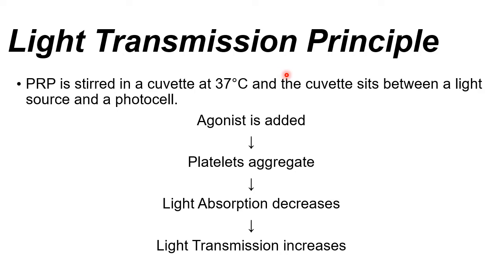Let's discuss the light transmission principle, which is similar to the spectrophotometry principle. We prepare PRP and warm the specimen at 37 degrees Celsius to simulate body temperature and activate the proteins for aggregation. Then we add the agonist. As platelet aggregation increases, more light passes through — light absorption decreases. Based on the spectrophotometry principle, absorption and transmission are inversely proportional. As more platelets aggregate, less light is absorbed, and more light is transmitted.